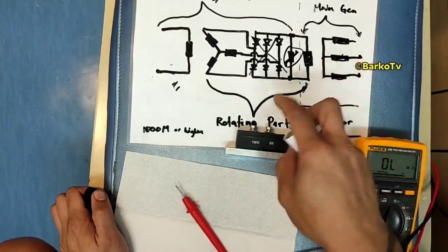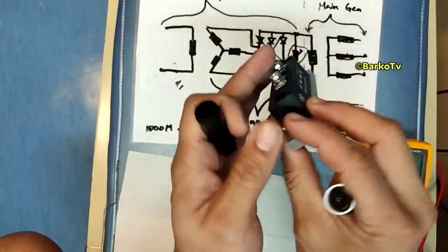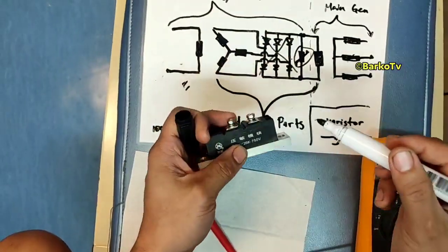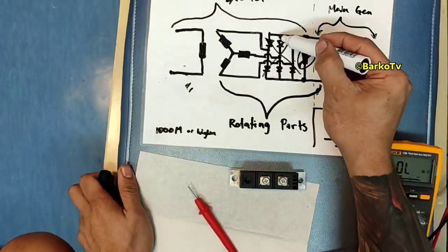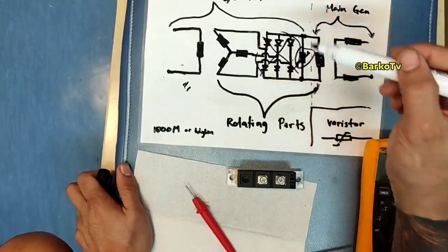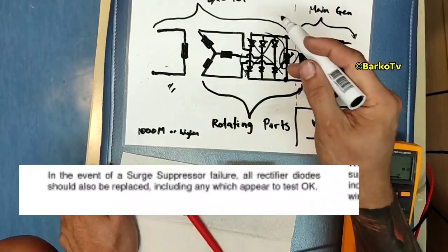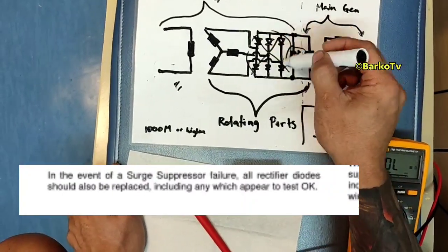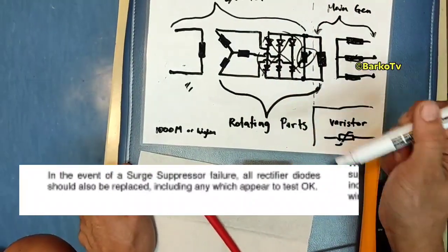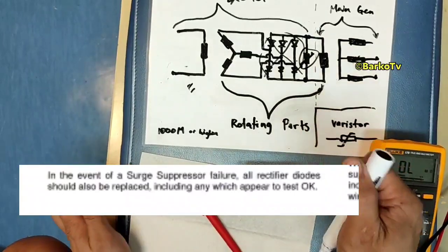If this varistor is damaged, as per manual you need to replace also the diode, even though you check the diodes and they are working, you need to change all of the parts as per manual.